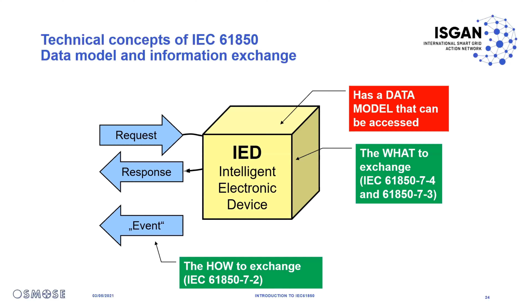A data model is hierarchically structured in a device, and depending on the function supported, we will find various elements. In the example here, we have a device that has a protection part, where we have some protection logical nodes, like a PDIS, which will be a distance element. We also have a control part, and in this control part, we have, as an example, a model of a circuit breaker, which is called a logical node — in this case called XCBR.